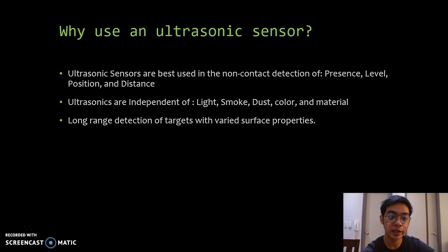So, here are some of the uses of an ultrasonic sensor. Number 1, ultrasonic sensors are best used in the non-contact detection of presence, level, position, and distance. Number 2, ultrasonics are independent of light, smoke, dust, color, and material. Number 3, long-range detection of targets with varied surface properties.